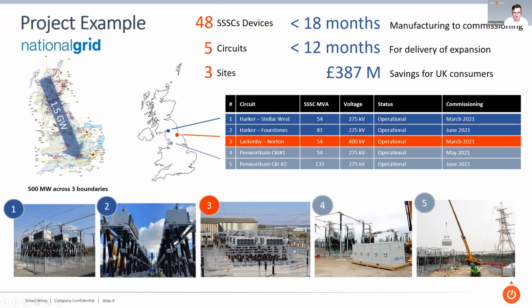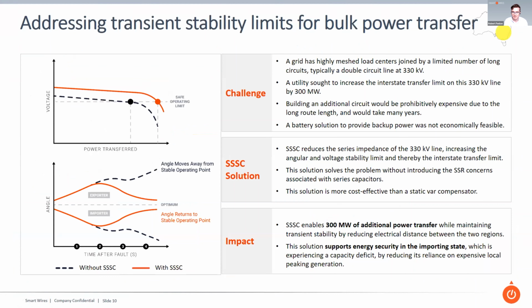The next application that I want to talk about is improving stability limits, particularly focusing on voltage stability. This was an application studied in Australia, in the southeast of Australia, where there was a meshed grid connected radially to generators, and basically they had reached the voltage stability limit, and also had issues with angular stability as well, but I'll focus on the voltage stability application, where the utility wanted to increase the transfer capacity by 300 megawatts. Building additional lines was going to be infeasible due to the cost and length of the actual lines between the generators and the demand centers, and this was also across a state boundary as well.